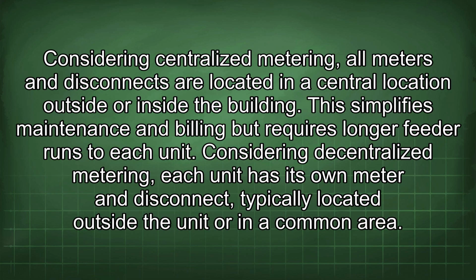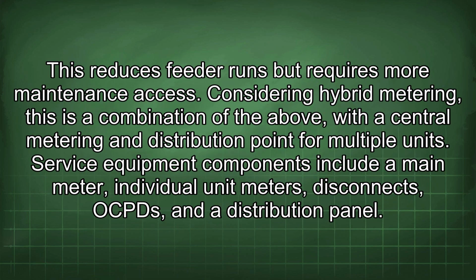Considering centralized metering, all meters and disconnects are located in a central location outside or inside the building. This simplifies maintenance and billing but requires longer feeder runs to each unit. Considering decentralized metering, each unit has its own meter and disconnect, typically located outside the unit or in a common area. This reduces feeder runs but requires more maintenance access. Considering hybrid metering, this is a combination of the above, with a central metering and distribution point for multiple units.